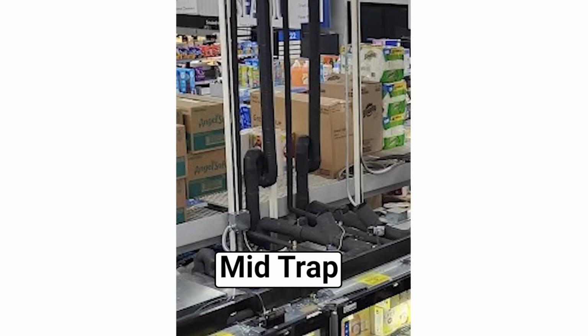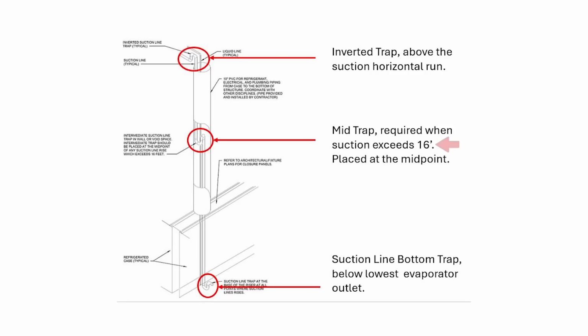Then the next place I'll have one is if that riser is really tall. And you talk about rules of thumb and refrigerant types and all that. I can tell you on a 20-foot run, you're going to have a trap in the middle, somewhere, right? Different rules for that, but there's probably going to be what we call a mid-trap, just because that is such an extreme distance to try to move oil suspended in vapor that sometimes it doesn't make it all the way to the top. It's gonna make it 3/4 of the way up and then fall. Well, we catch it in that mid-trap and then it can try again, and it's only got to go half as far. So that works out pretty well.